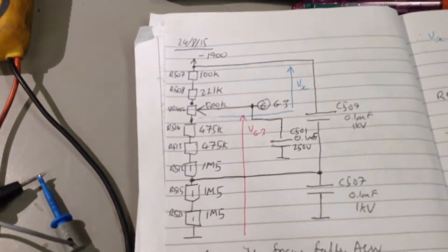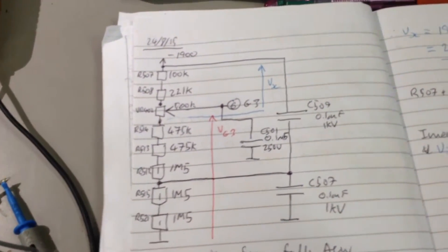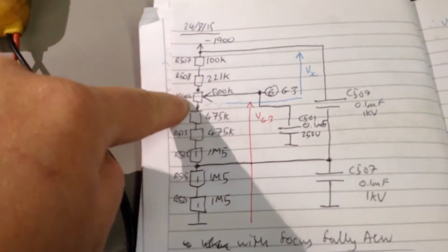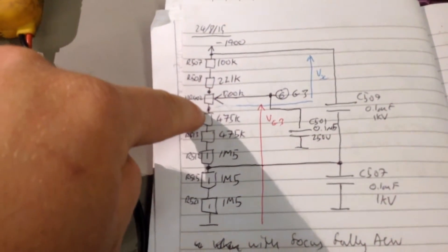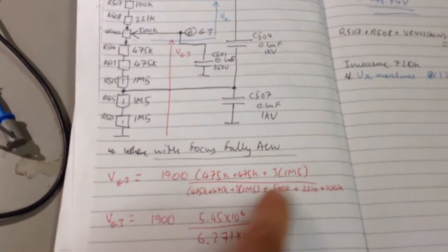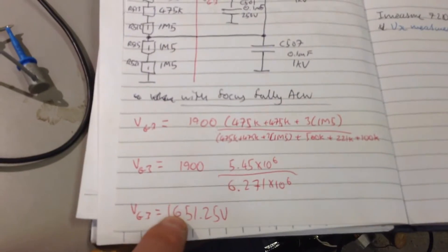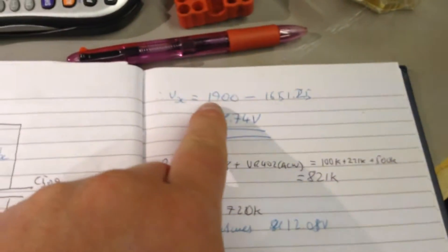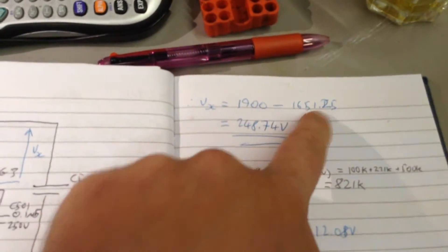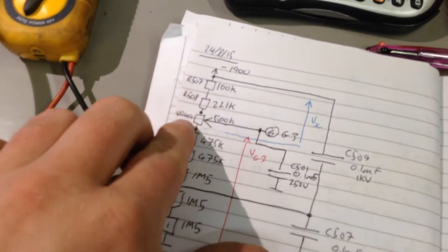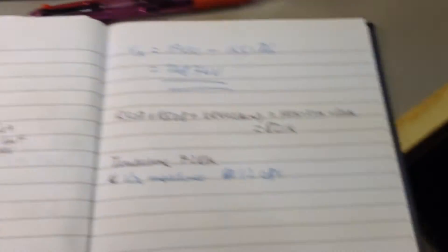So what the problem is, is that I'm measuring here. I'm measuring Vx, and this is Vg. I have turned this fully anticlockwise, so this point to here is definitely zero volts. So using potential divider, Vg should equal 1,651.25 volts. So that's Vg3 to Vx should equal 1,900 minus that, which should give you 248.74 volts. And just for the sake of argument, R507, 508, and Vr402 should equal 821k.